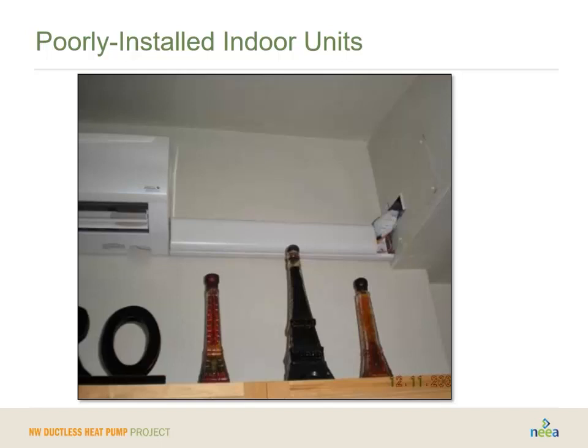Now let's take a look at some poorly installed indoor units. Now this device may actually work well, and I'm very glad that they used a line set hide on the inside, because where they had to come through was not directly behind the head. But they've left this ugly hole above the bottle on the right. It's not sealed and it's not covered. And they actually make elbows or turns for line set hide that would have done a terrific job to cover that. So this was a matter of just not having the appropriate piece of line set hide on hand. But that's an easy to fix problem.